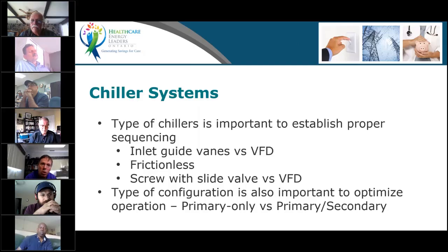If you have a more modern chiller, you can use what we call variable flow primary only. Most of the older systems are primary-secondary, and your secondary loop has a set of pumps which you can put on variable speed, while your primary pumps with the chiller can remain constant speed, so your chillers are humming away happily without flow variation. So that's something you need to know. It will affect the measure.